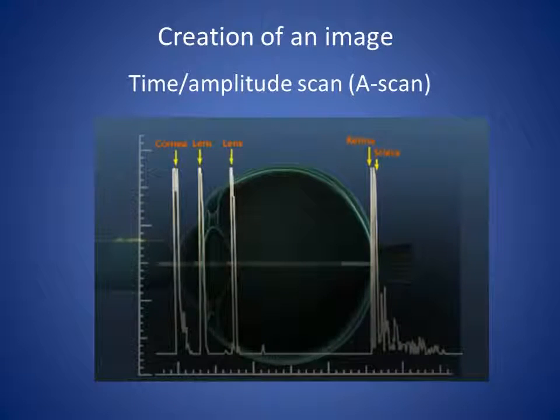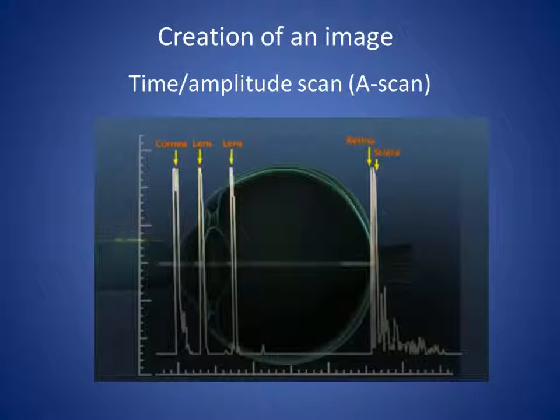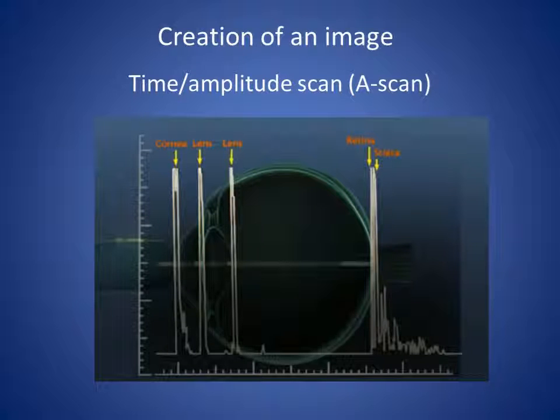Each layer of tissue in the body produces a separate reflection of the ultrasound signal. In the original type of scanner, these reflections were simply displayed on the screen of a cathode ray oscilloscope. This results in a trace where the x-axis represents time and the y-axis represents the amplitude of the reflection — that is, how strongly the sound is reflected. Each layer producing a reflection shows up as a peak on the trace, giving rise to the name of the technique: an amplitude, or A-scan.